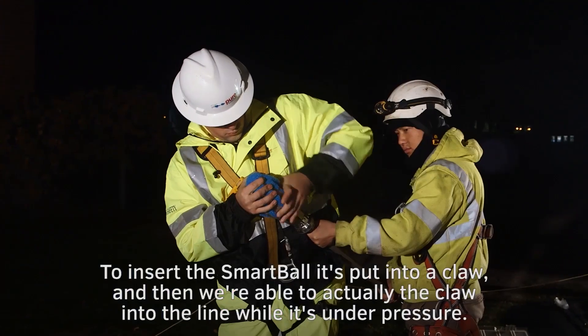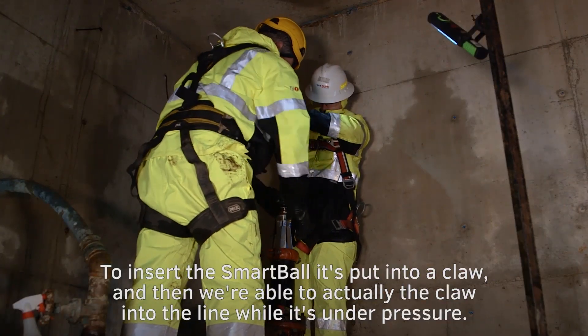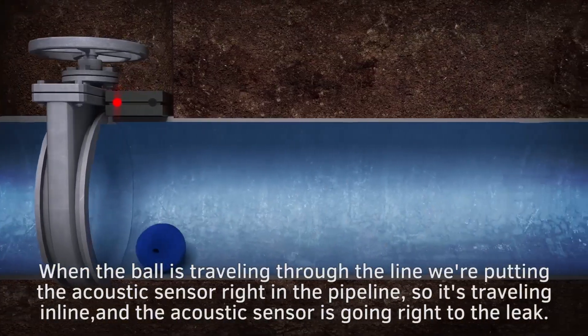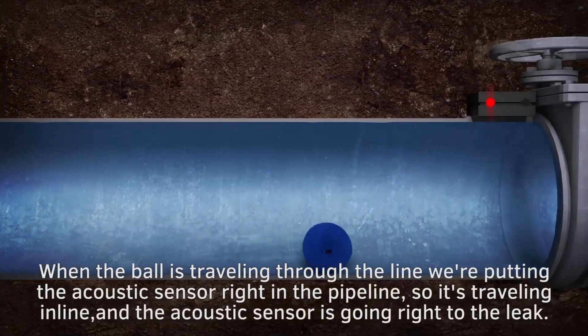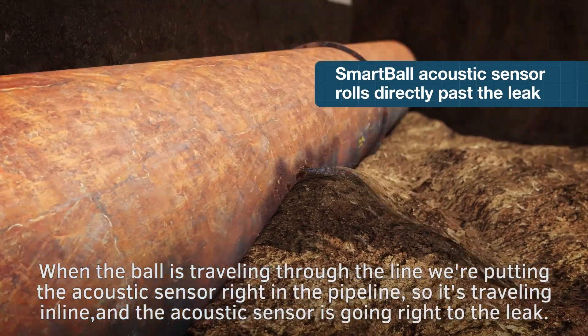To insert the SmartBall, it's put into a claw and then we're able to lower the claw into the line while it's under pressure. When the ball is traveling through the line, we're putting the acoustic sensor right in the pipeline so it's traveling in-line and the acoustic sensor is going right to the leak.